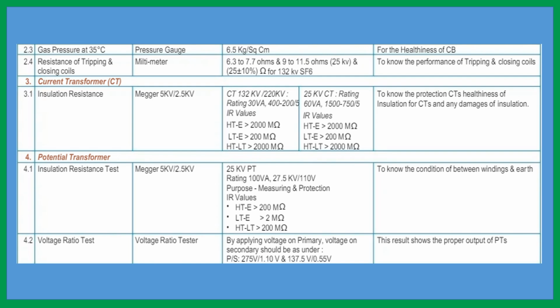Next is potential transformer. All these things will be measured by 5 kV or 2.5 kV megger. For all HV and LV, you have to measure this thing with 5 kV or 2.5 kV. 25 kV PT, LV PT rating is 100 volt ampere, 27.5 kV or 110 volt. Protection system is using 110 volt.